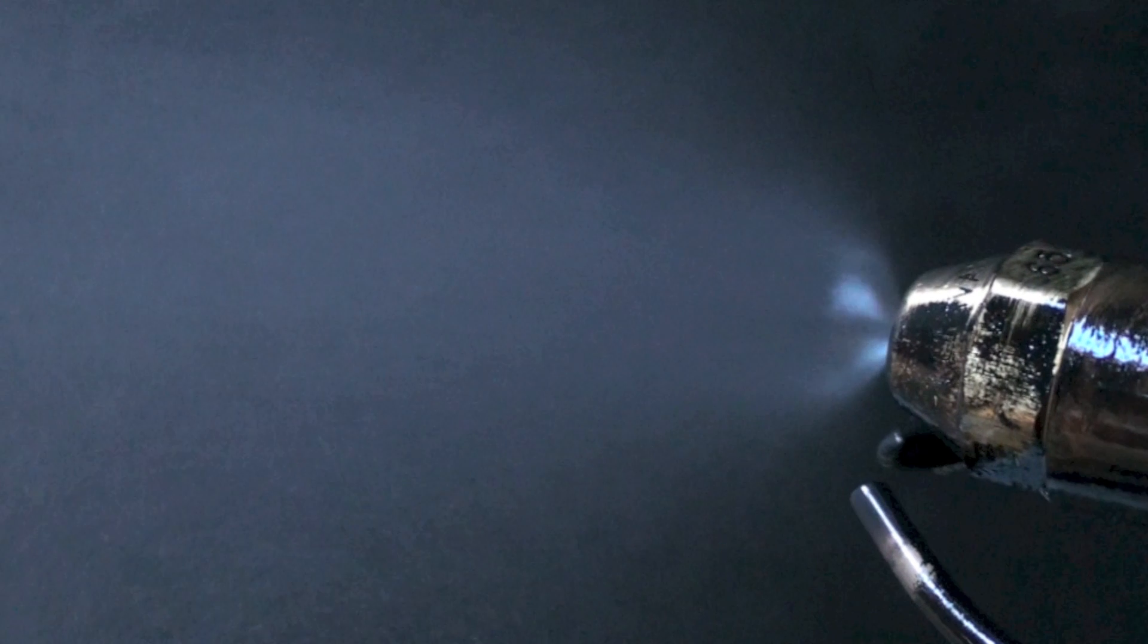That's how it really should be. So a minimum of 100 pounds and go with recommendations on the furnace. Many of them are up to 140 pounds now. The higher the pressure, the better the atomization.